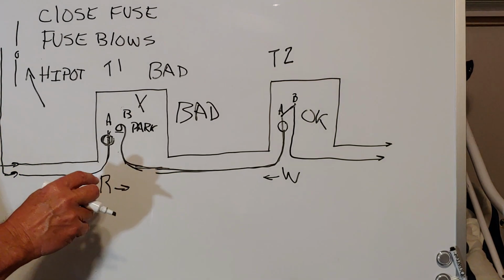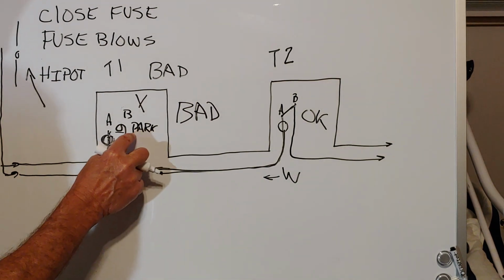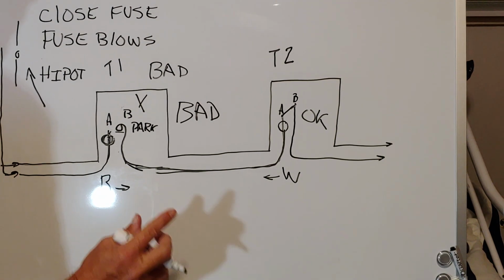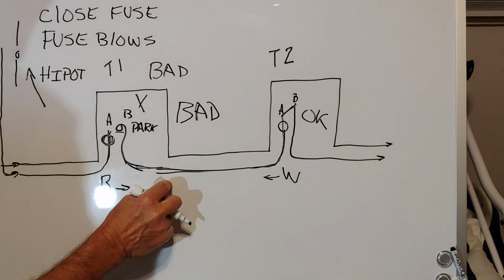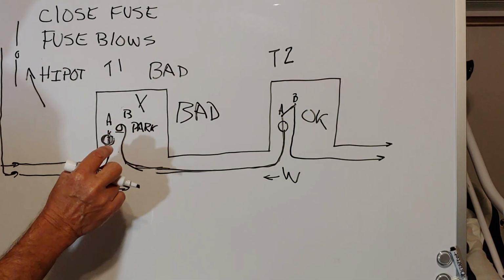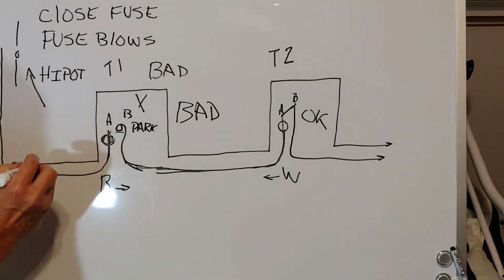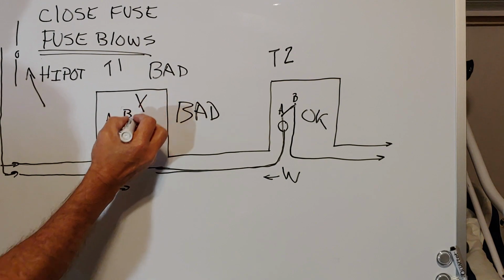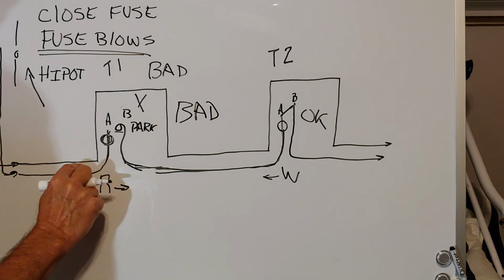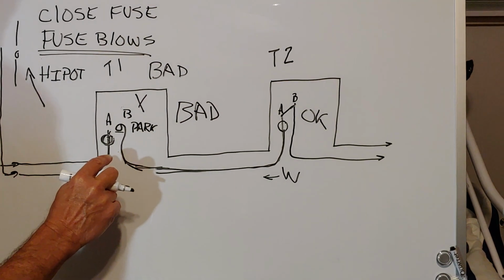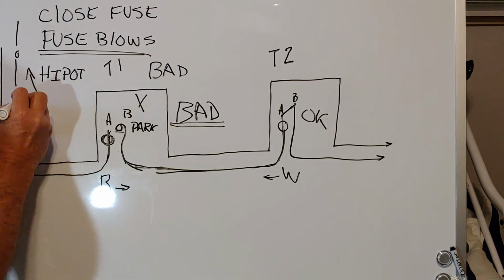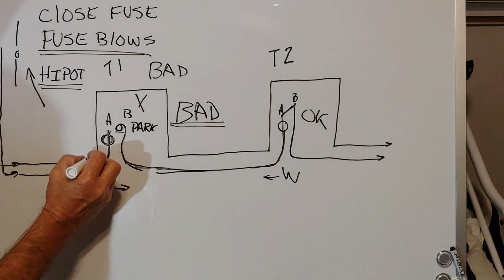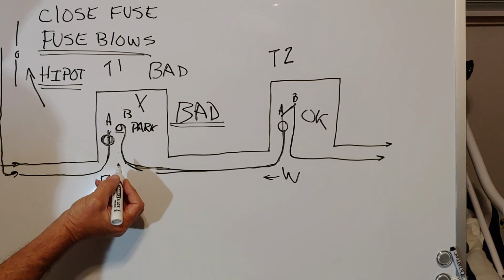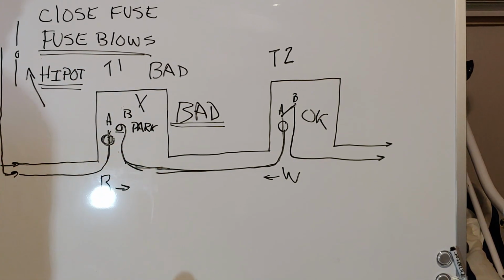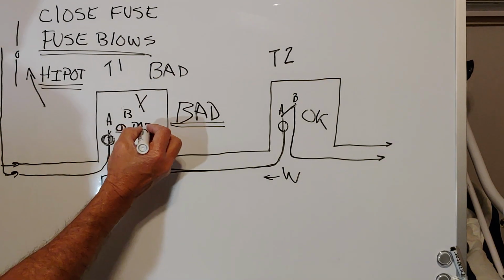Okay, in summary, we're typically going to go out and have a red and a white and suspect the cable. All right, we're going to have to go ahead and stand off the B wire because we think it's in this span, the outbound span between here and here. We're going to have to do that to be able to get this transformer back on. You reclose the new fuse. The fuse blows again. All right, now the transformer is very suspect. You may have a fault in A, but that's really in the A cable. But we suspect that the transformer is bad. Hipot across here to your cable, you're going to have to remove this off. So remember, you have to isolate this. You have to take this off and park it also. Hipot. That span shows good in your hipot sticks. The transformer is no good.